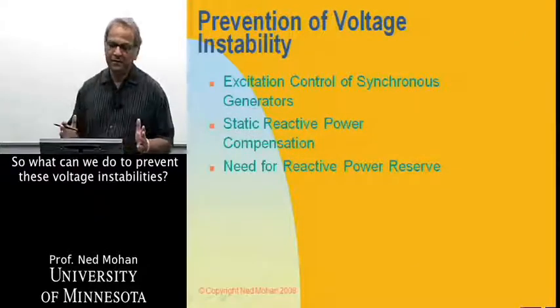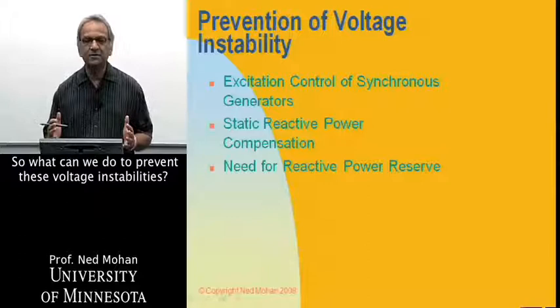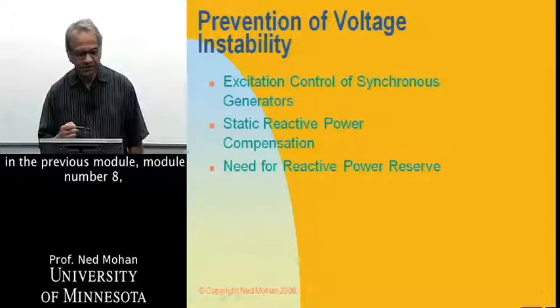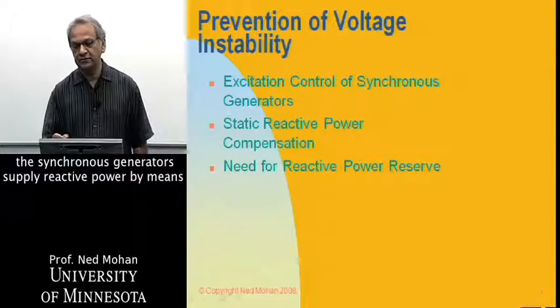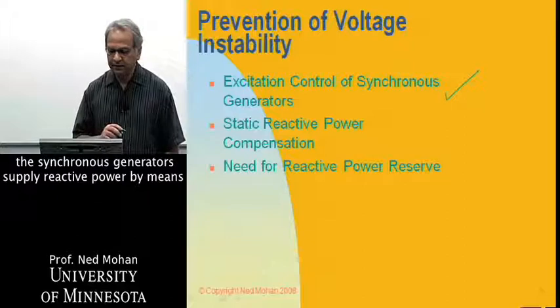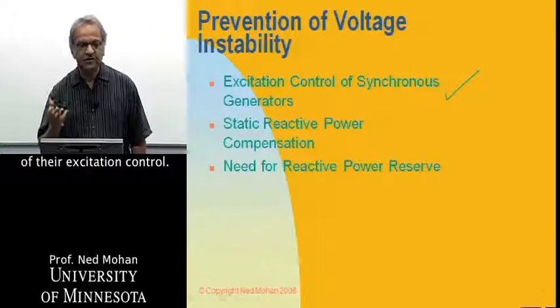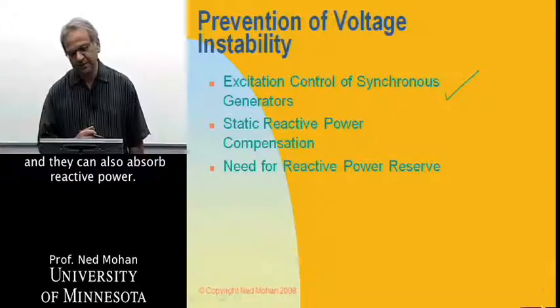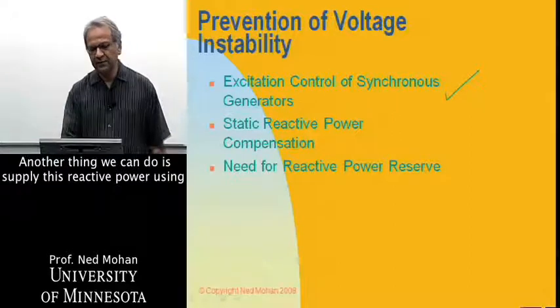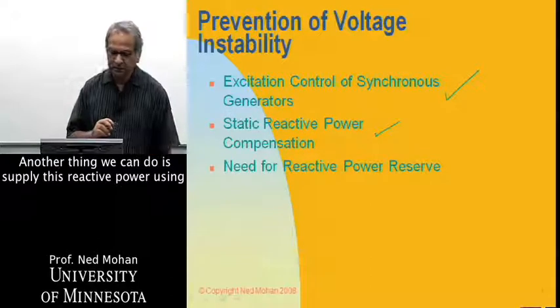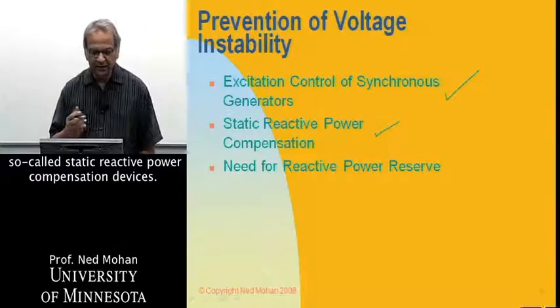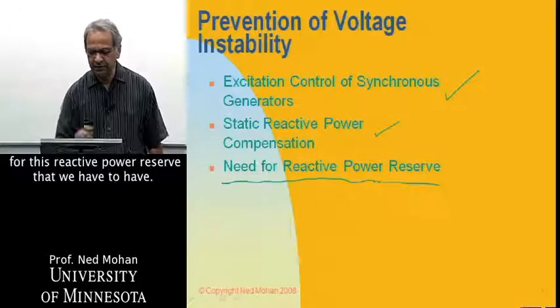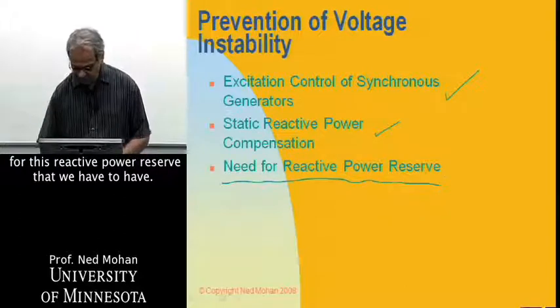So what can we do to prevent these voltage instabilities? One of the things we can do, as we saw in module number eight on synchronous generators, is that synchronous generators supply reactive power by means of their excitation control. They can supply reactive power, and they can also absorb reactive power. The other thing we can do is supply reactive power using static reactive power compensation devices, which shows the need for reactive power reserve.